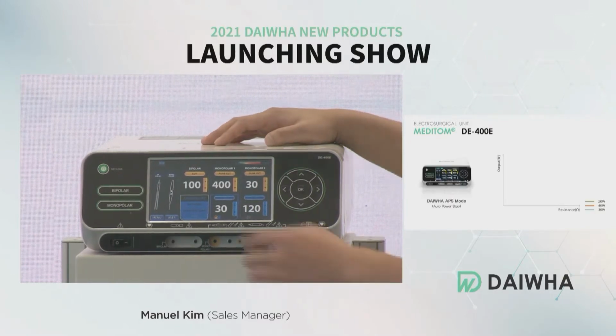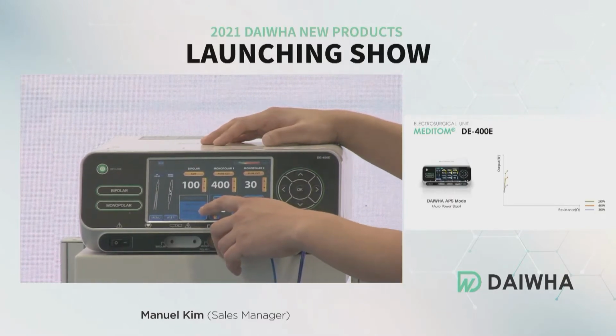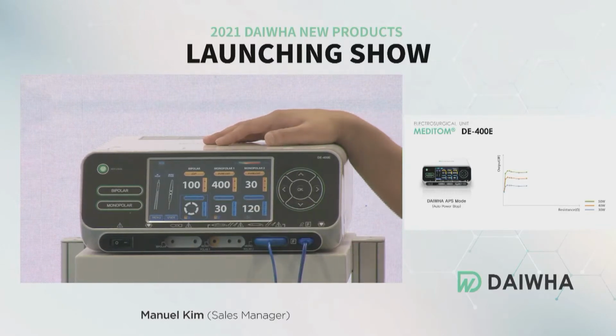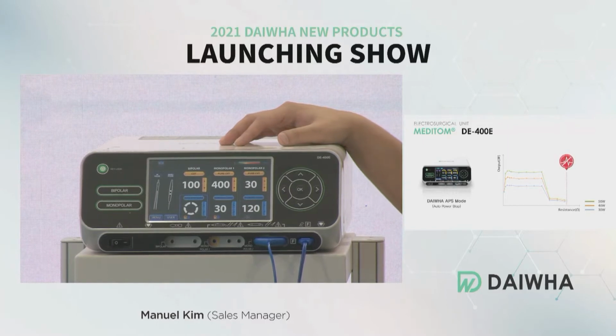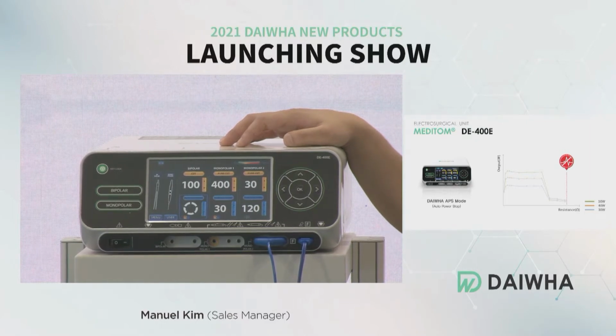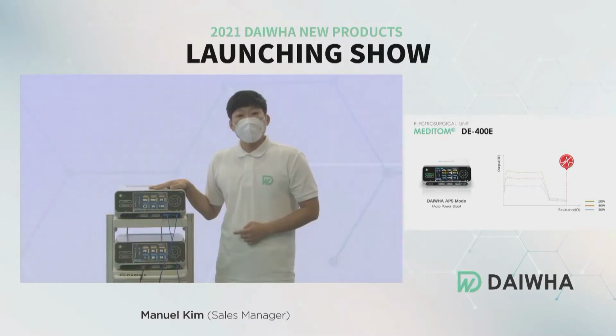Especially, there is auto power stop mode in bipolar coagulation. We call it APS mode for short. APS means that the power output is cut off after reaching a certain resistance value. In other words, the power output is automatically cut off when the bipolar coagulation is done.